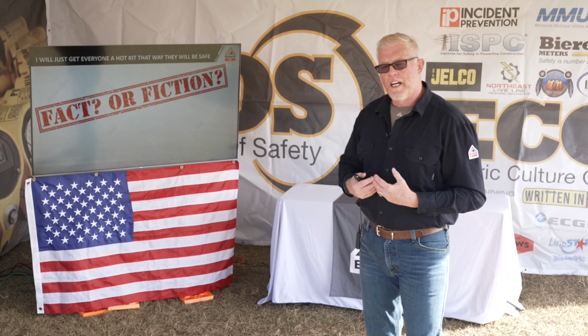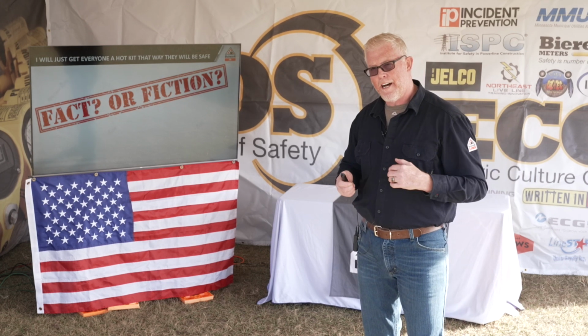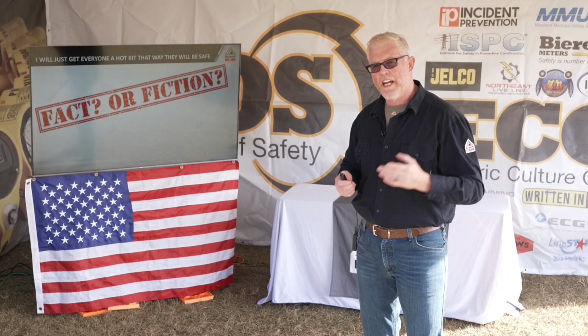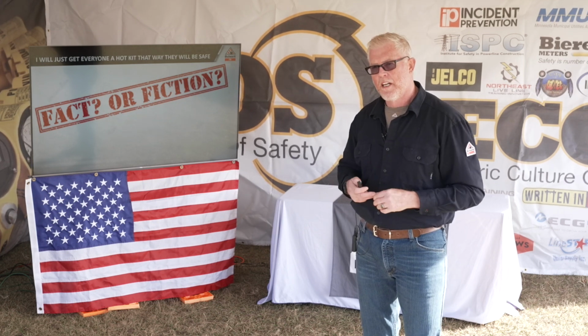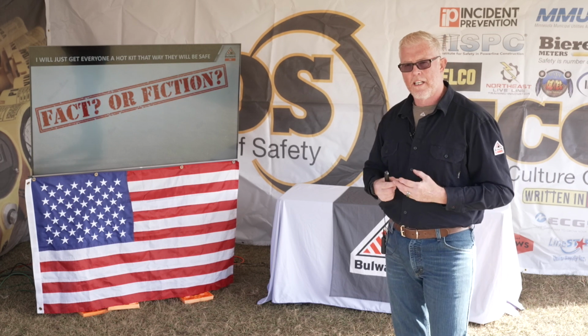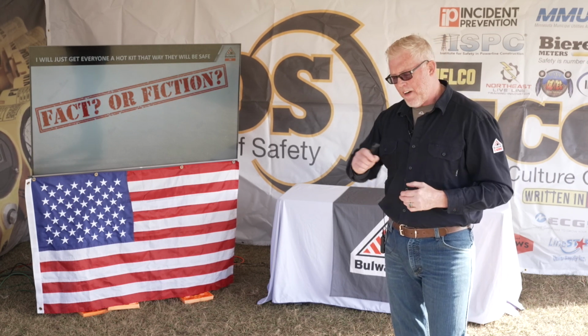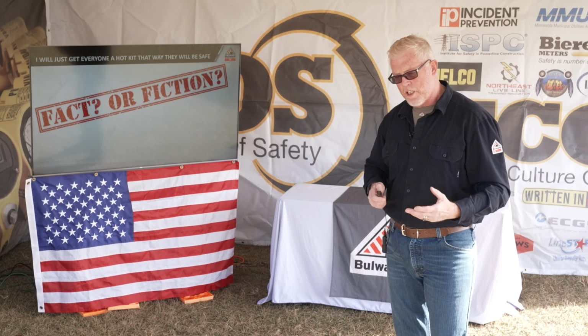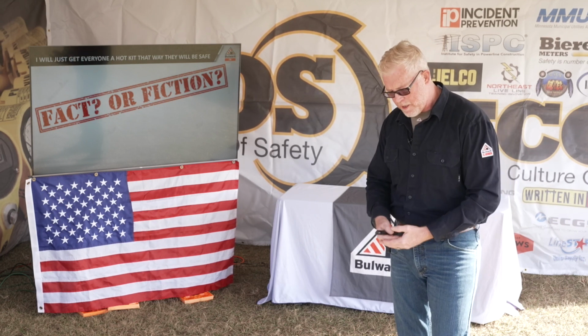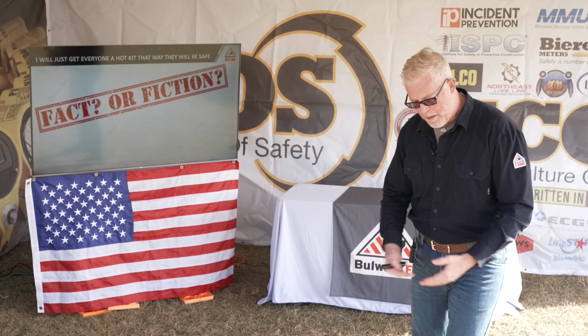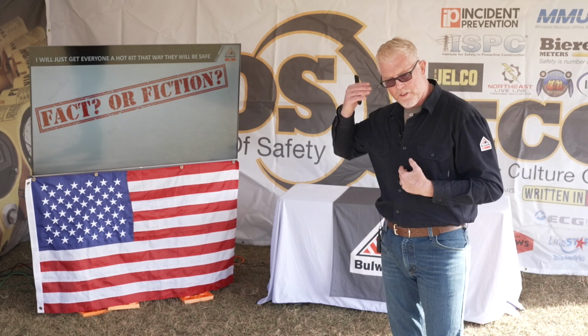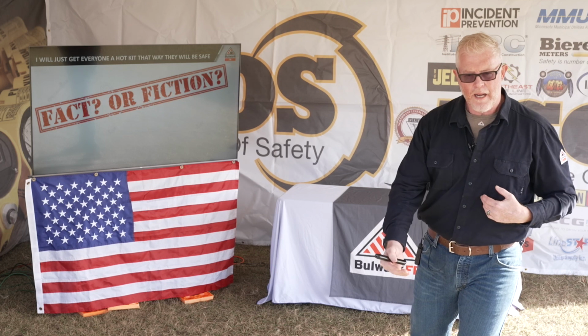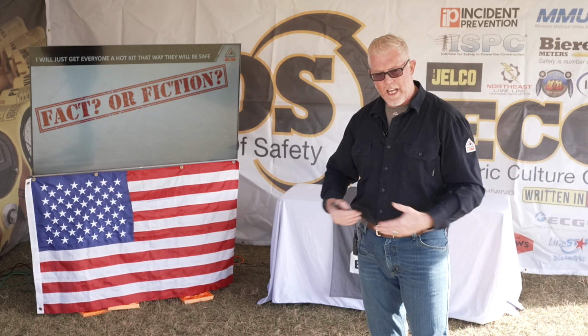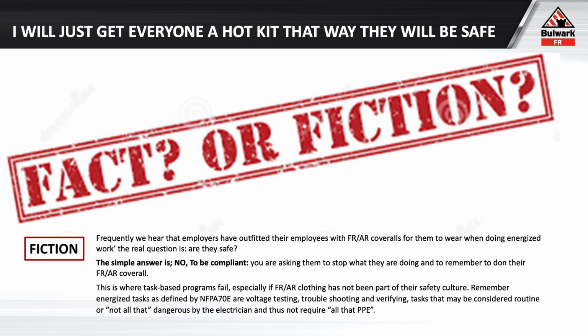This is more to my electrical contractor community. Think of it this way: I'll just get everyone a hot kit and that way they'll be safe. That's kind of the difference between being compliant and safe. If I check my list that all my electricians have their hot kit, in that kit I've got them an arc-rated coverall, their rubbers, their leathers, their hard hat, face shields, balaclava, hearing protection, eye protection, insulated tools, and that kit is outfitted to every electrician doing energized work during the day. What's the downside of that?